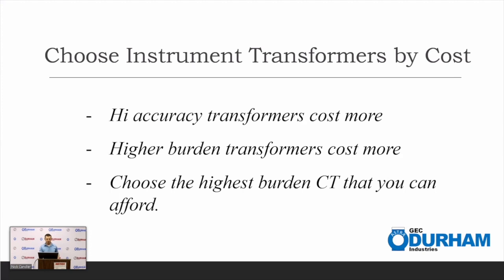So you want to choose your instrument transformers by cost, not just by cost out of pocket, but cost back in your pocket. Investing a little bit more in a high accuracy transformer is actually going to save your utility some money. Might cost you a little bit more. Higher burden transformers are more costly as well. So you want to choose the highest burden CT that you can afford.